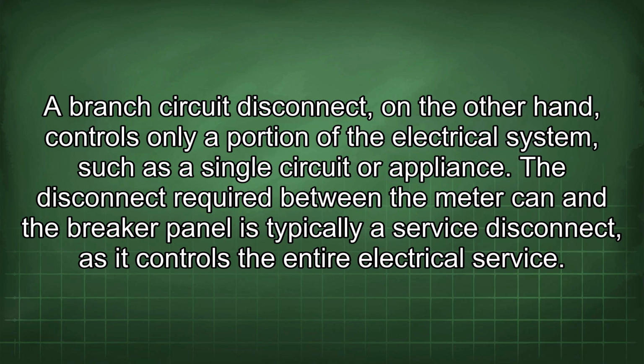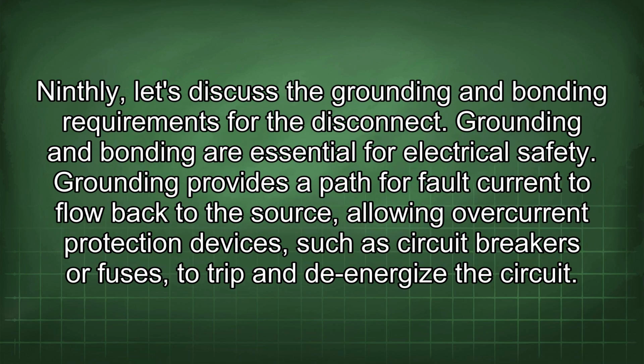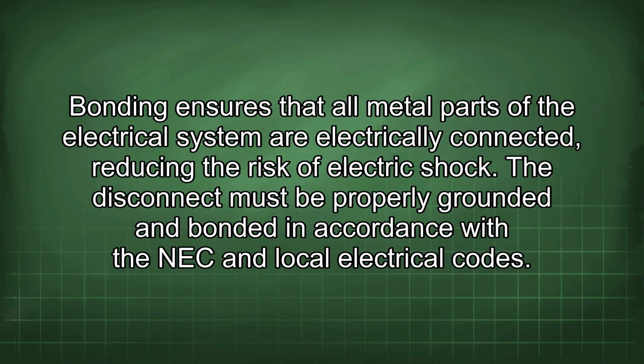Ninthly, let's discuss the grounding and bonding requirements for the disconnect. Grounding and bonding are essential for electrical safety. Grounding provides a path for fault current to flow back to the source, allowing overcurrent protection devices, such as circuit breakers or fuses, to trip and de-energize the circuit. Bonding ensures that all metal parts of the electrical system are electrically connected, reducing the risk of electric shock. The disconnect must be properly grounded and bonded in accordance with the NEC and local electrical codes.